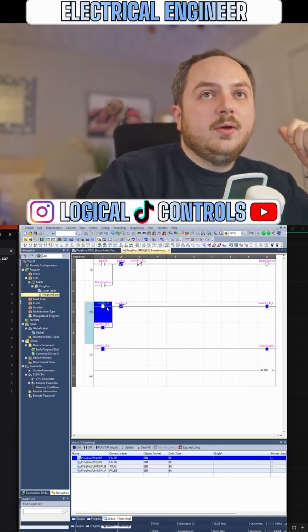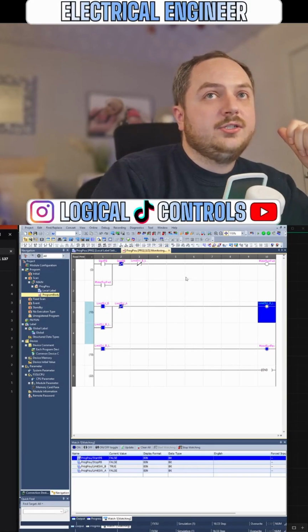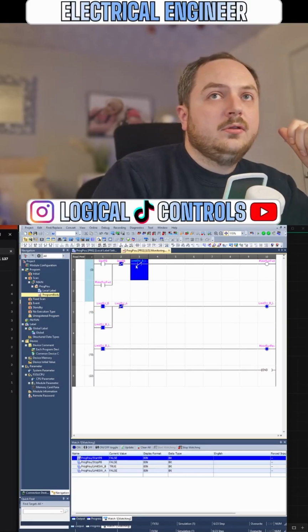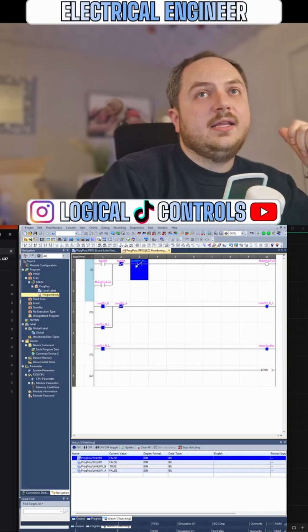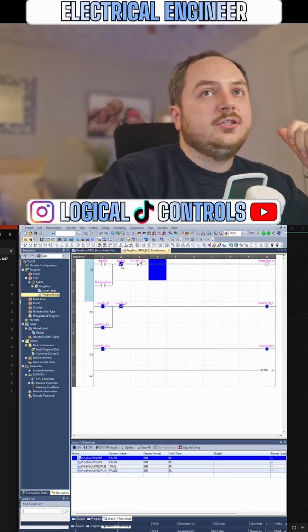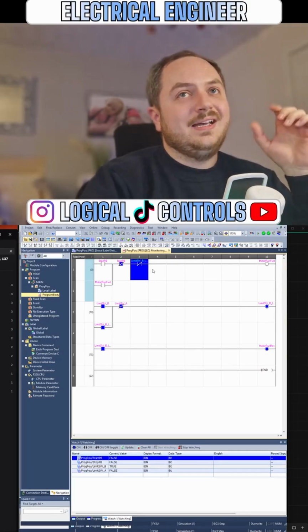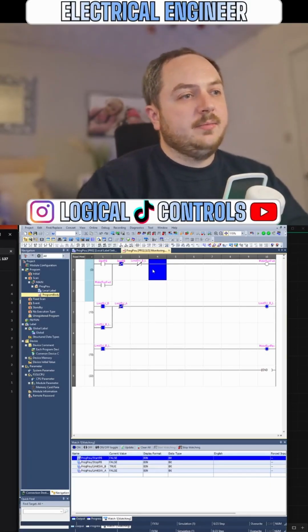So when we hit limit switch B, we activated this coil here, limit switch B latch. That's what opened the motor forward run coil, so that's open at the minute. I know it shows as closed, but it's not in blue - you see how the stop button's in blue? This one isn't, because it's normally closed, but it's activated, so that means it's open.